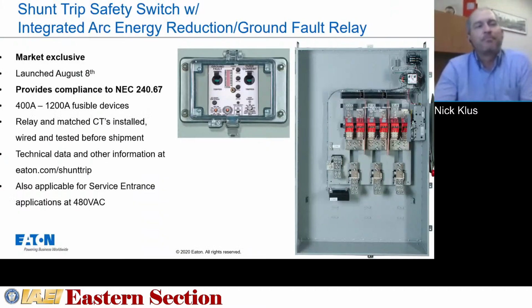But today, if you want to go to the next slide, Tom, one thing of particular interest, especially for this audience, is 240.67, which as was mentioned earlier, applies to having some sort of plan or product to integrate arc energy reduction on 1200 amp and above fusible devices. Obviously 240.87 has been around for a while relative to circuit breakers, and Eaton's approach there has largely been our ARMS feature that Manny was talking about. When the code drove us to 240.67, that presented an interesting situation for us in the fusible safety switch world, because with circuit breakers we'd addressed it, as Manny said, through the trip unit or bypassing the trip unit through some technology to make it act quicker.